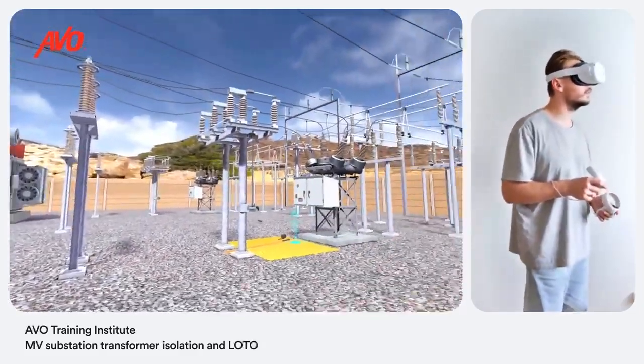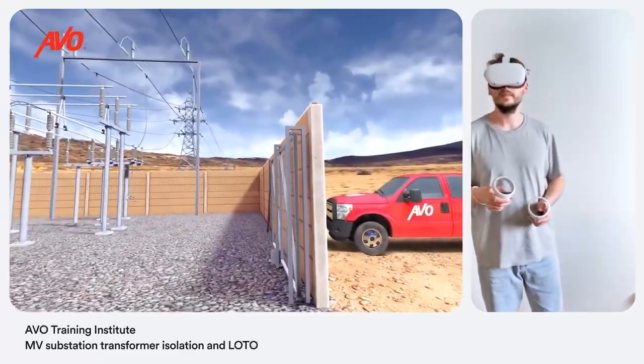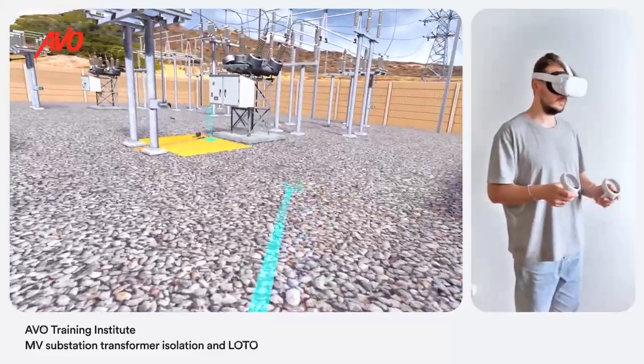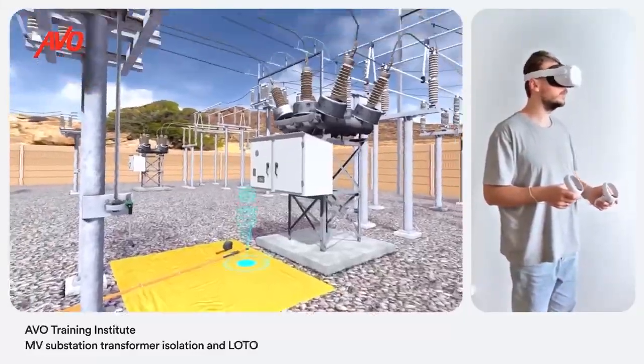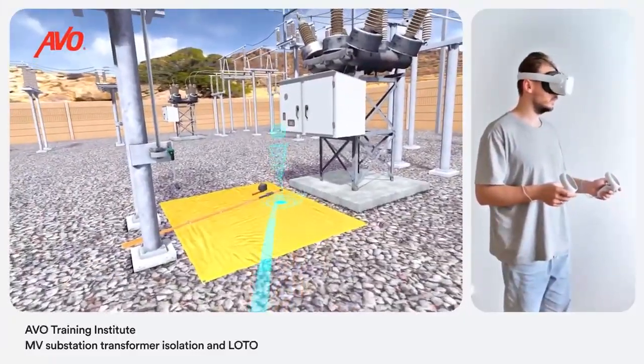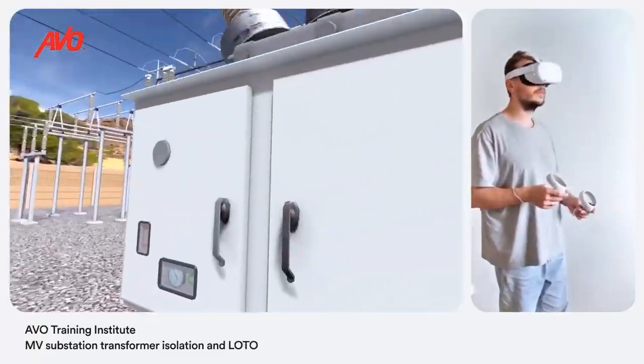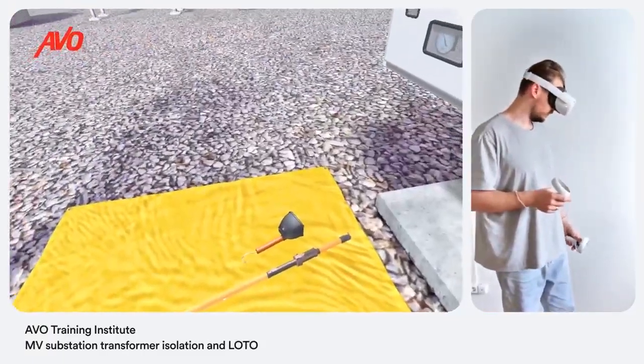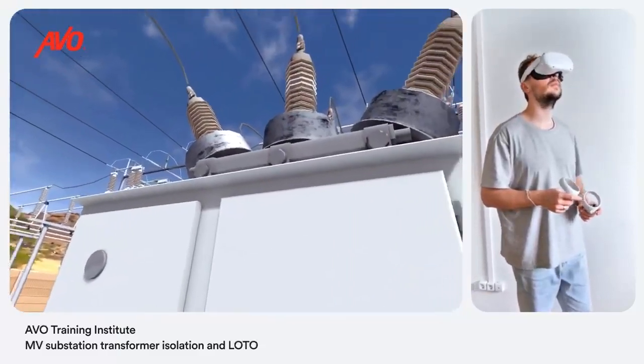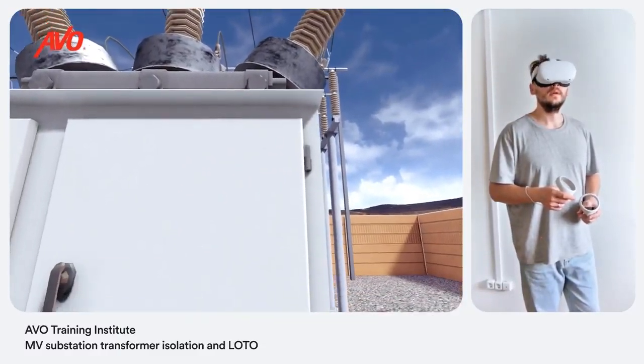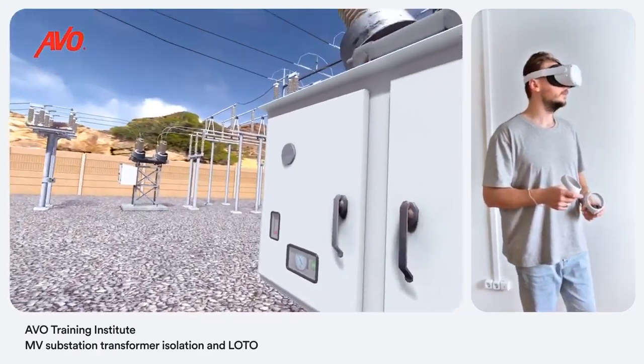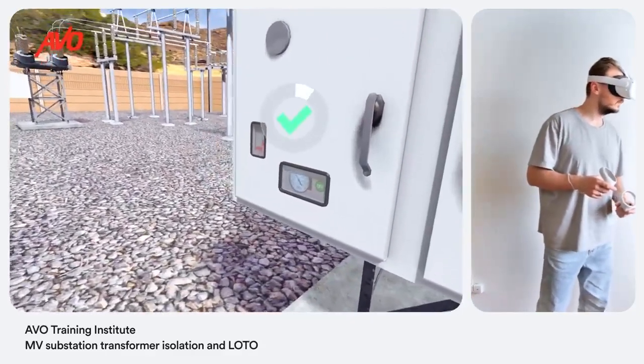Having identified apparatus for work and familiarized yourself with the substation layout, you can start isolating the medium voltage substation transformer. Verify that the feeding SF6 circuit breaker is in the open position. First, stand in front of the SF6 circuit breaker control panel and verify the contacts are in open position through the contact position indicator.